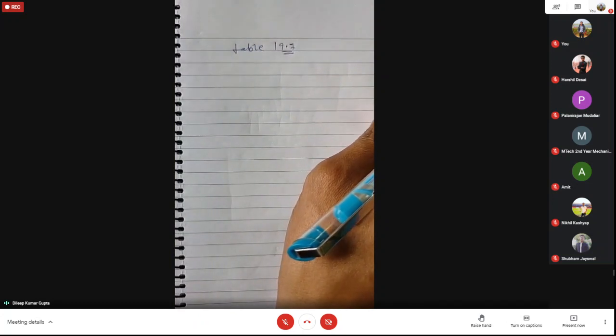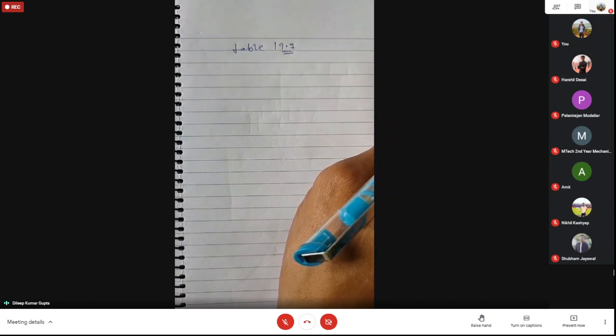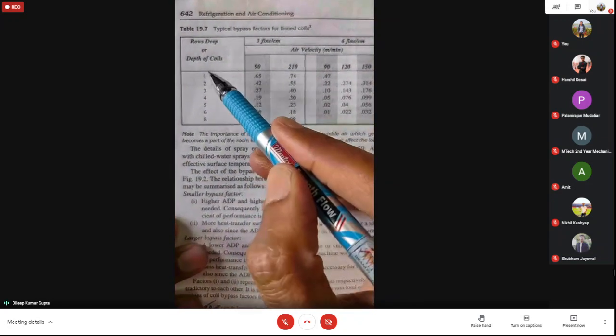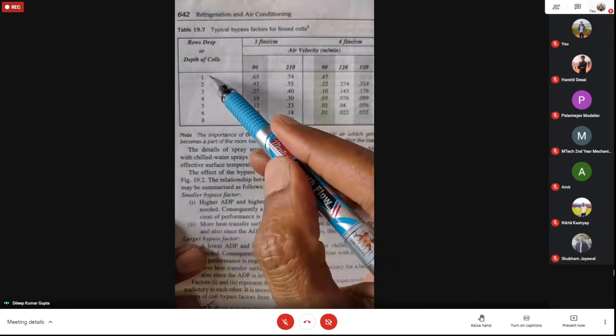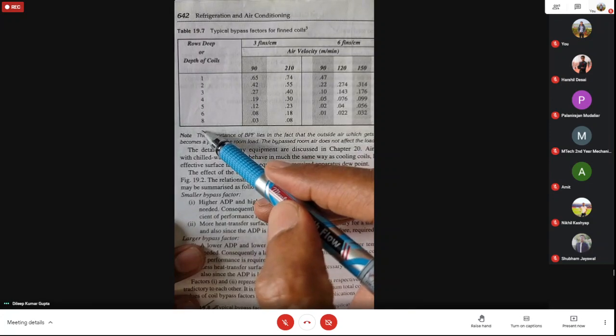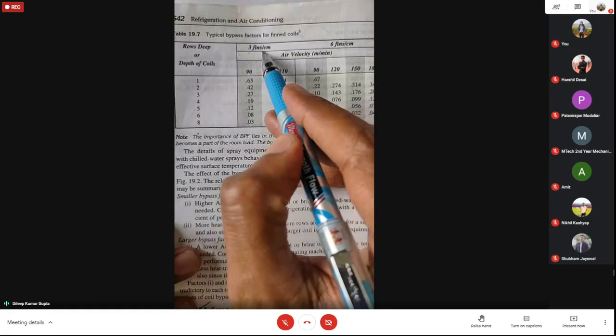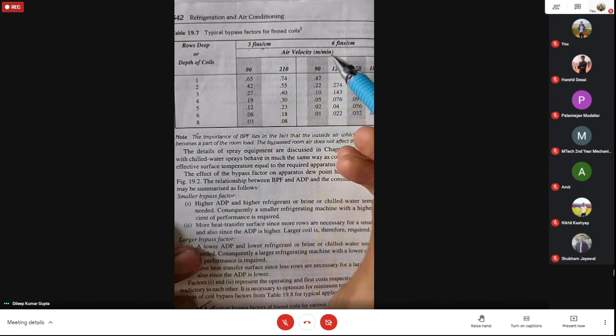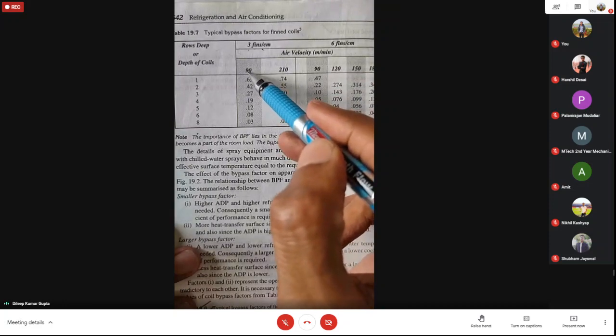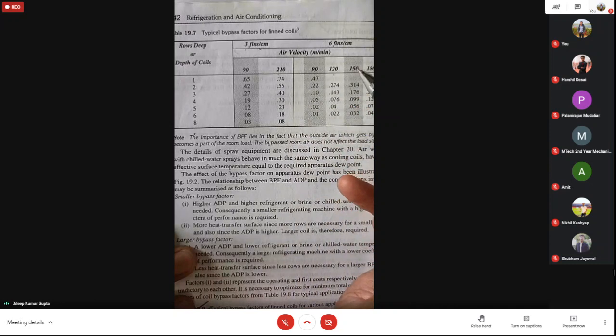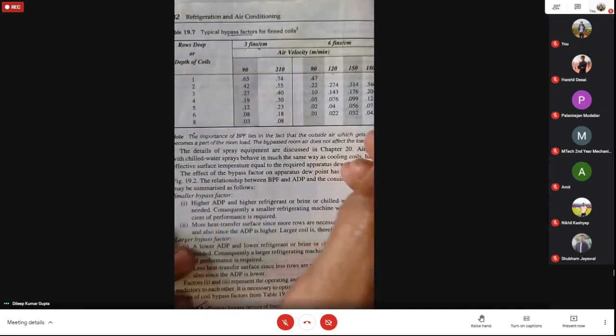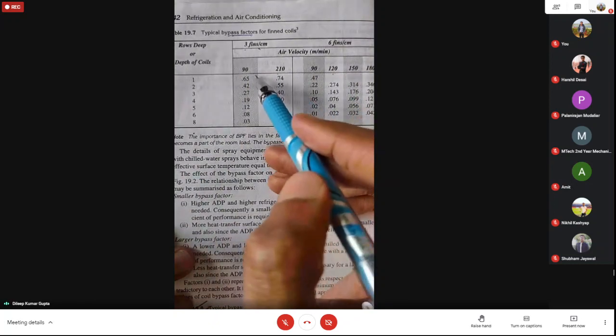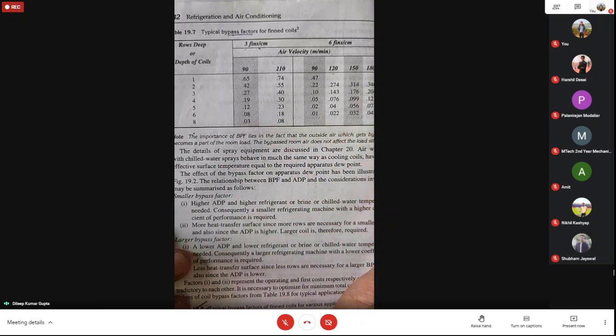You refer to the table and find the range of row depth, number of rows, fin size, and air velocity recommended for a particular system. For example, in this table, if you are going for 1 row, 2 row, 3 row, 4 row, 5 row coil, up to 8 rows, along with a fin spacing of 3 fins per centimeter of length, the air velocity in meters per minute will be 90, 210, 90, 120 under these conditions. Then you get a typical value of bypass factor for a fin tube type arrangement. These are completely experimental data.